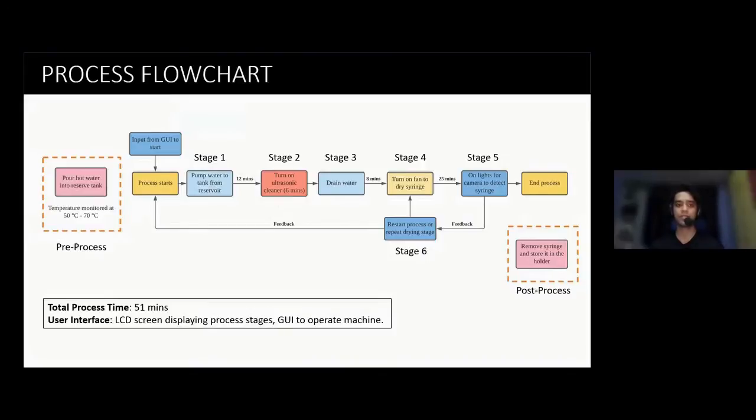In the pre-process, the nurse is required to pour hot water into the reservoir tank, which will be monitored at 50 to 70 degrees Celsius. As for the main process, when the process starts, water is pumped into the tank from the reservoir, and the ultrasonic cleaner is turned on for the cleaning.